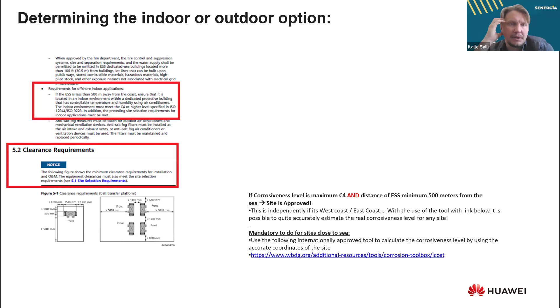For indoor installations, there are fire safety requirements. For instance, the wall surrounding the ESS should have a fire resistance of at least 2 hours. There are also minimum distances required between the ESS and surrounding surfaces. On the right side, for indoor installation, there should be at least 1.2 meters from the closest wall, and on the back side, 3 meters from the exterior wall to the closest other building if there are other buildings nearby. These are the specifications for distances in indoor and outdoor installations.